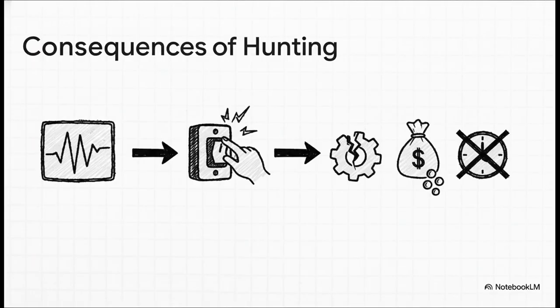And listen, this isn't just some minor wobble, the consequences are really severe. When the generator overshoots, it can try to push power back onto the grid, which instantly trips a safety breaker. The whole system shuts down, meaning lost savings, someone has to manually reset it, and you're putting incredible stress on very expensive machinery. It's a total recipe for failure.